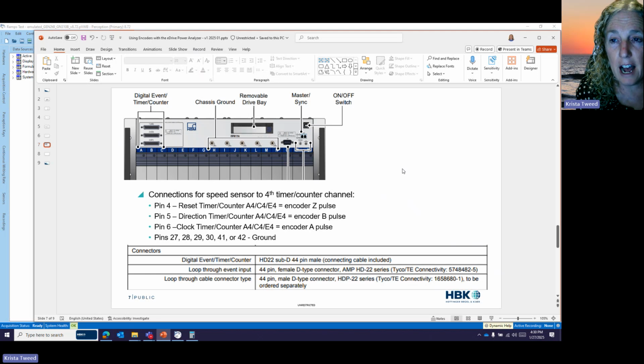So let's step through a few things about how this connection is going to work. To back up just a minute and talk about how the timer counter channels get connected to the GenDAQ mainframe. This is just a picture of our 17-slot mainframe. Each slot is designated a letter, and you can see the mainframes will have either 1, 2, or 3 of these 44-pin D-sub connectors, and they are labeled AB, CD, or EF. The reason for that label is that the digital inputs and timer counters are actually supported by the modules in the slots, there's just not room on that front panel of the module to make the connection. So the connectors are on the mainframe, but these connectors can only be used if there are modules in the corresponding slots that support those channels.